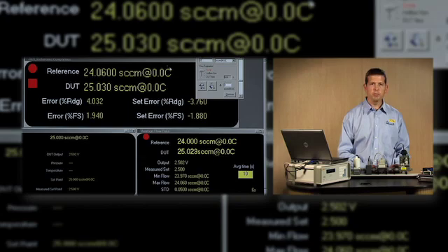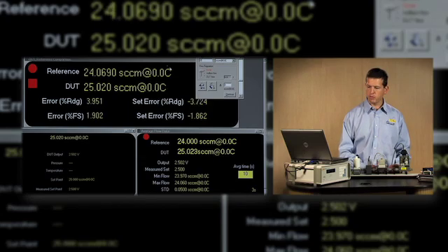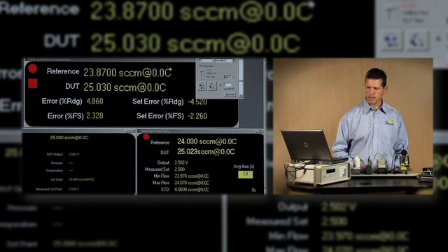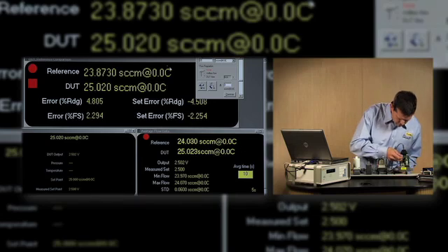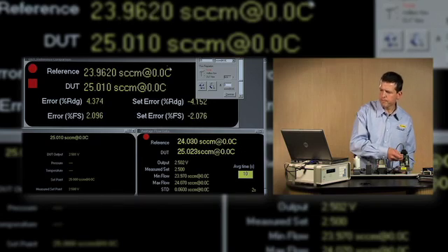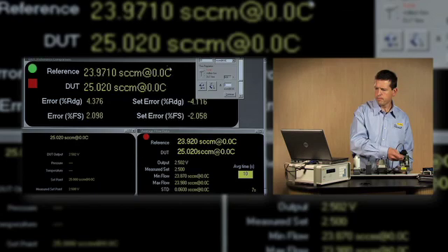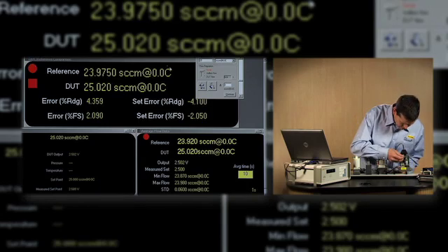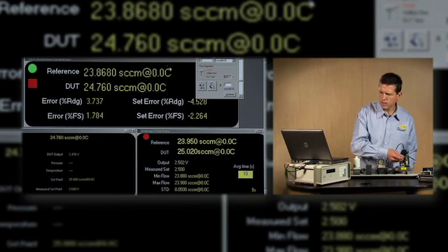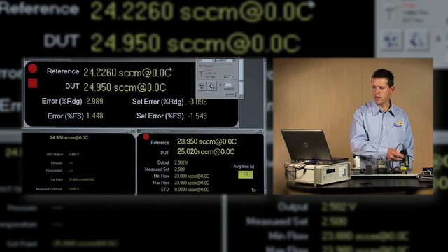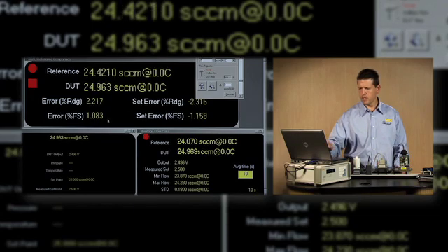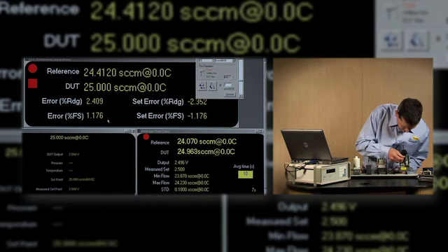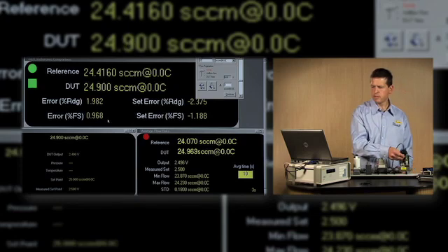Our worst point during the initial run was at the 50% point where we were high by over a percent, almost 1.4%. So I'm going to need adjustments on this point to bring it down quite a bit. Again, I'm watching that error percent full scale indication next to the cursor and bringing that down to within 1%.